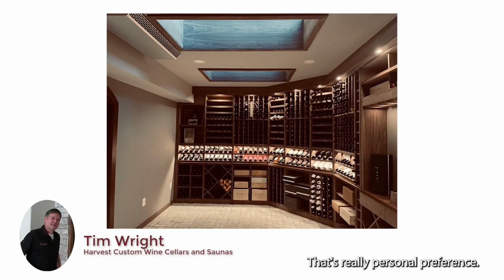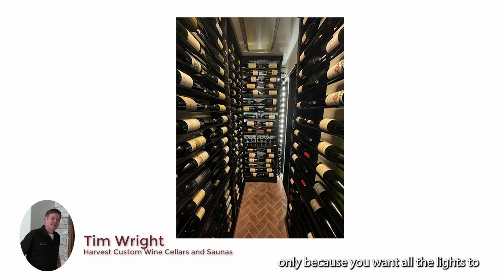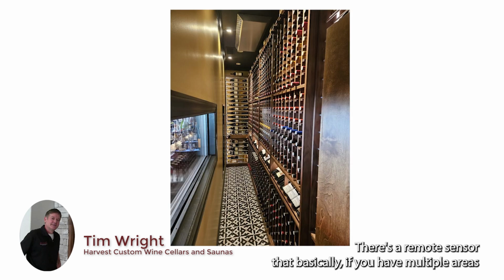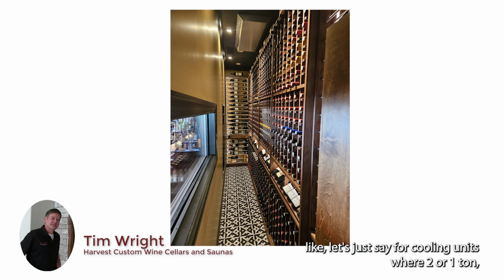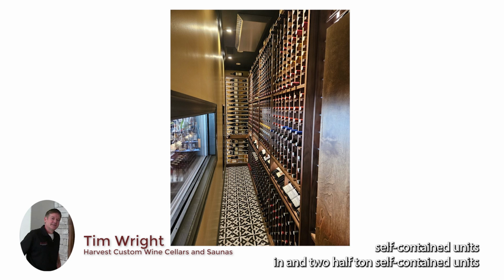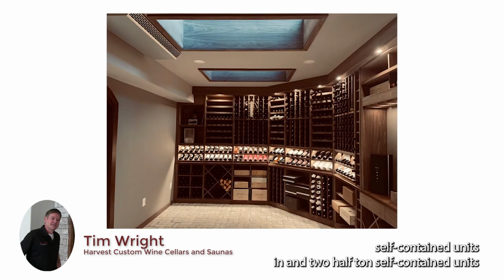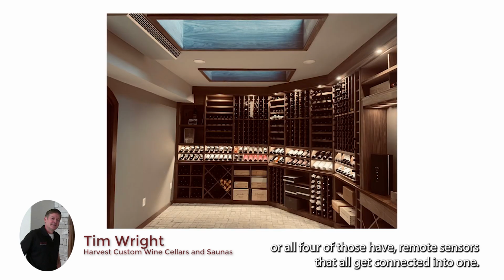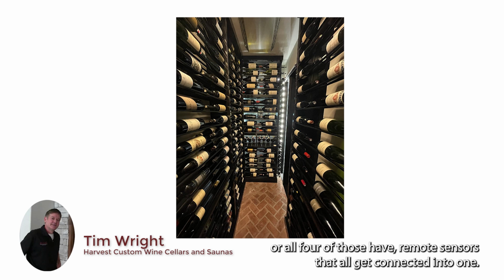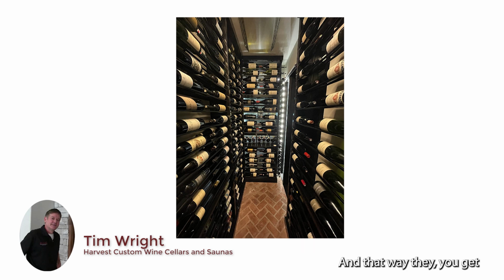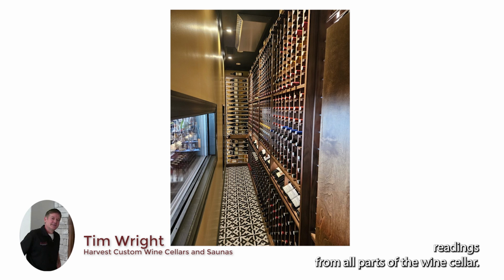That's really personal preference. The ones that I've done have all been connected onto one, only because you want all the lights to come on at the same time, the same temperature and humidity. There's a remote sensor that basically, if you have multiple areas, like let's just say 4 cooling units where 2 are 1 ton self-contained units and 2 are half-ton self-contained units, or all 4 of those have remote sensors that all get connected into one, and that way you get readings from all parts of the wine cellar.